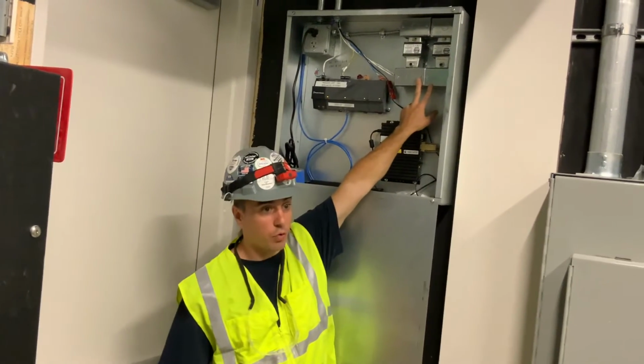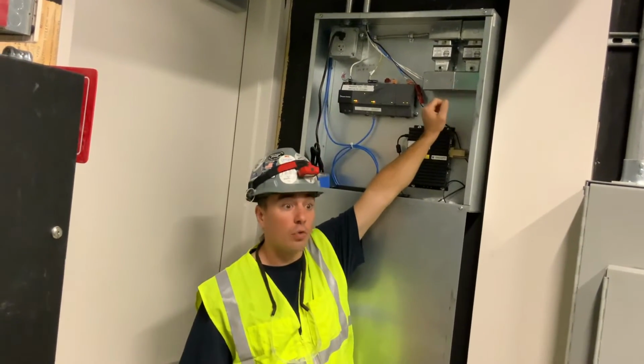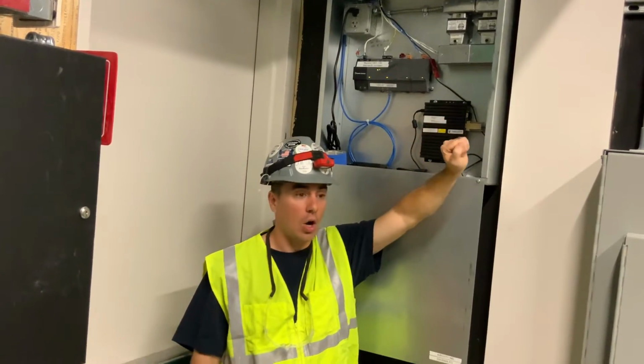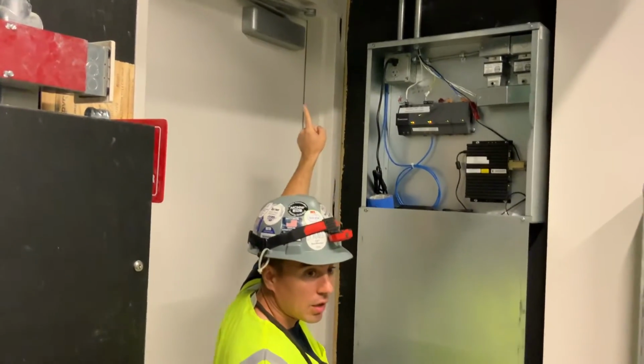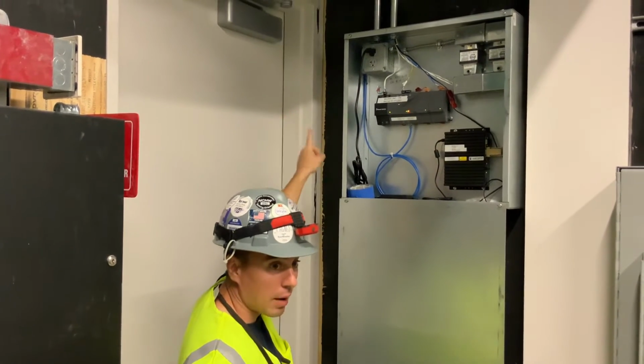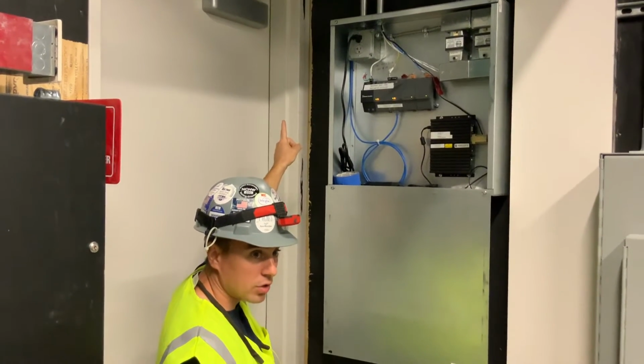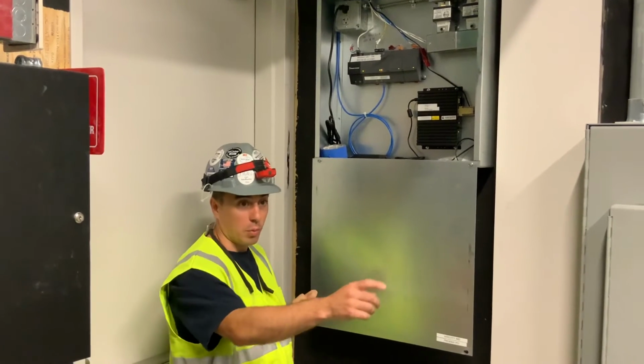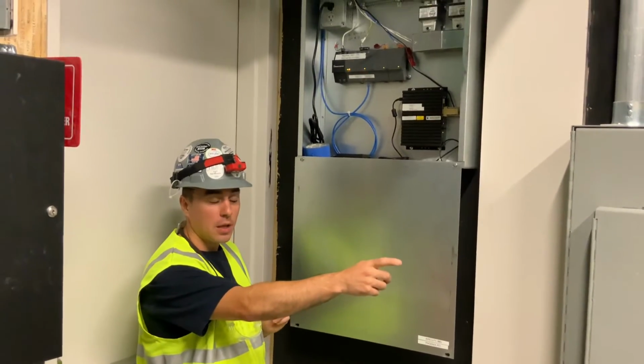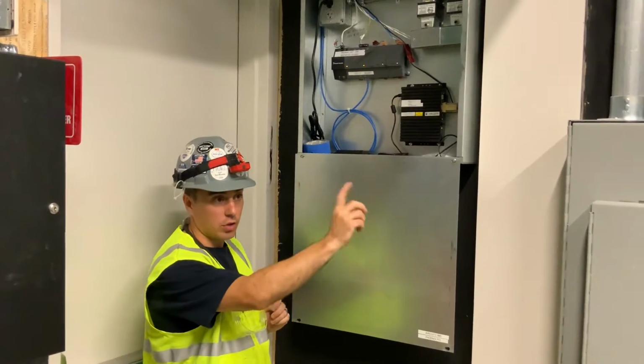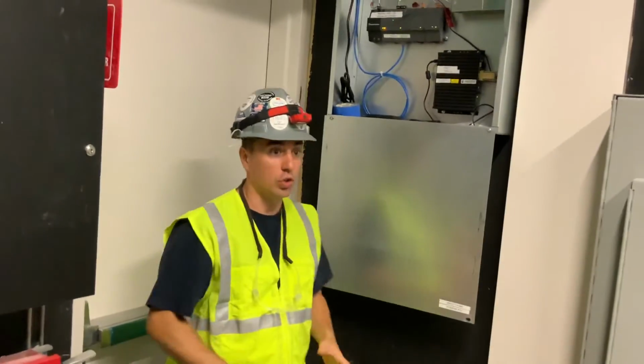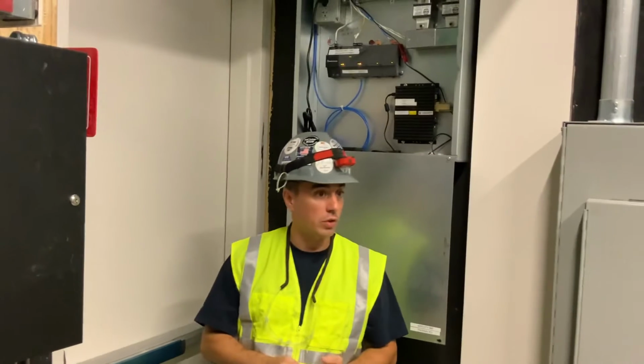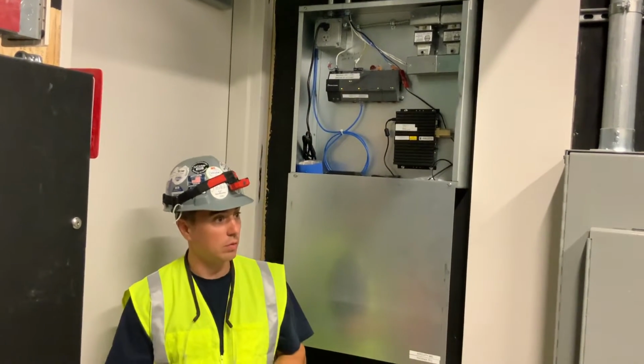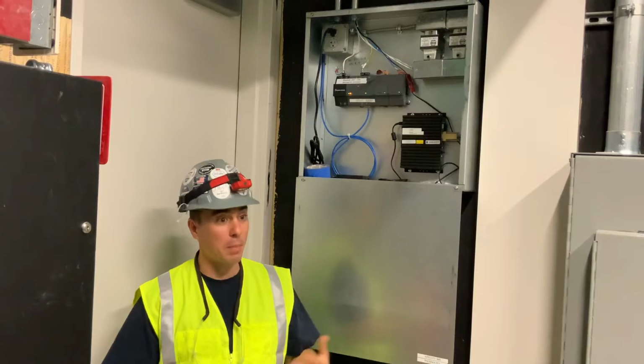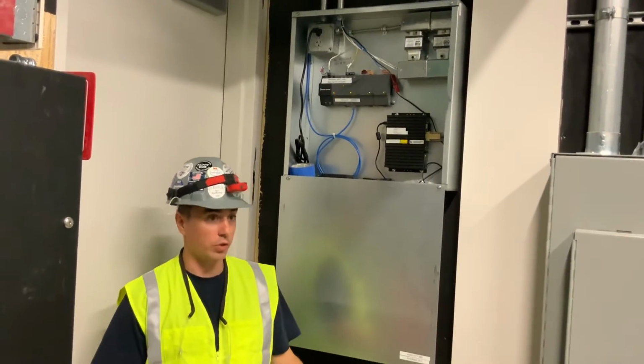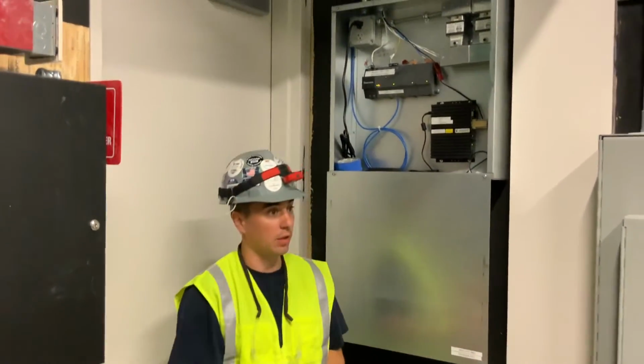Here are the transformers for AIRCUITY. Transformers for Phoenix are outside of this electric closet in the hallway, kind of over top of this door and over top of the elevators. And the other transformers for Phoenix are on the other side of the building in the other electric closet. As soon as you go in the door, you have them up, and they are labeled with what valves they are operating. So if you ever have a power issue, that's where to look for your 24 volts. It's either going to be outside this door or in that next electric closet.